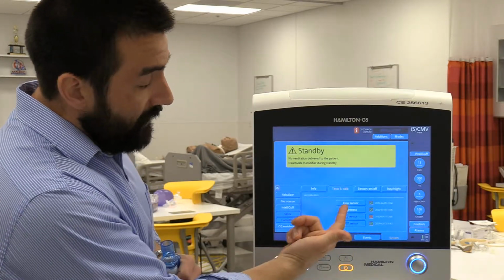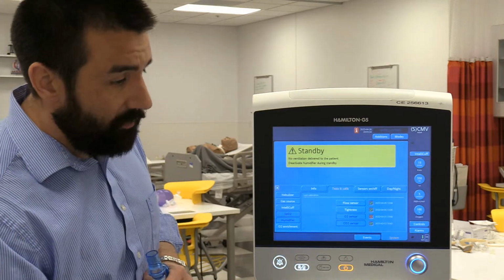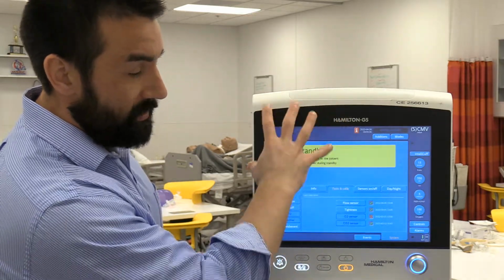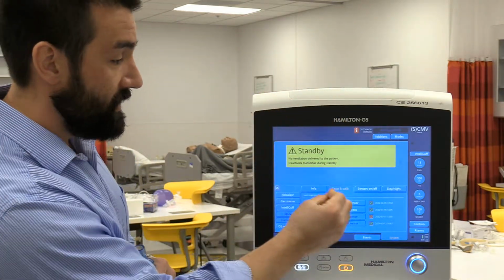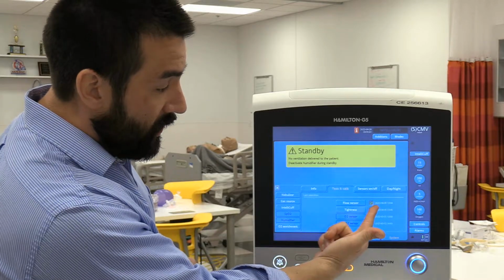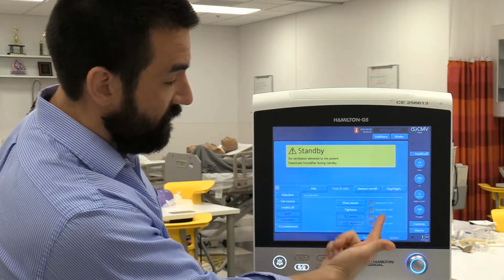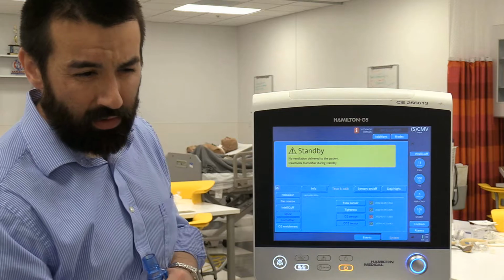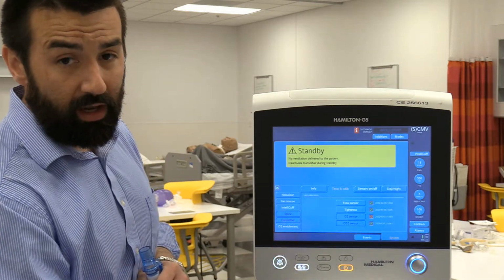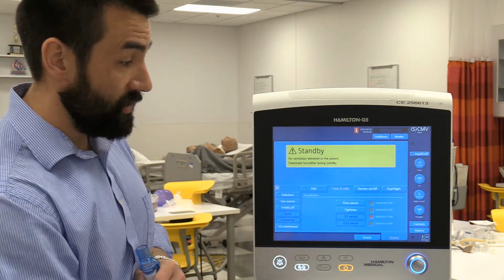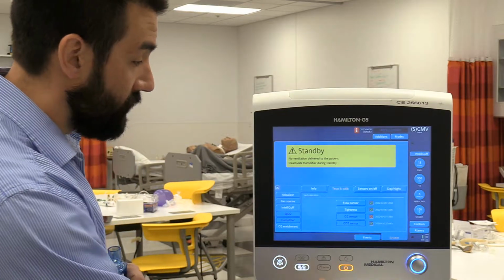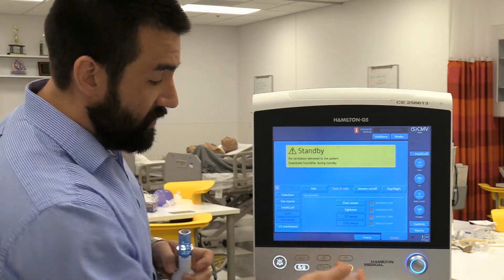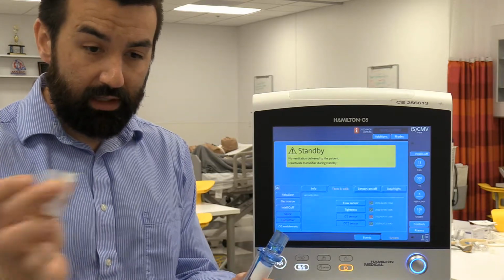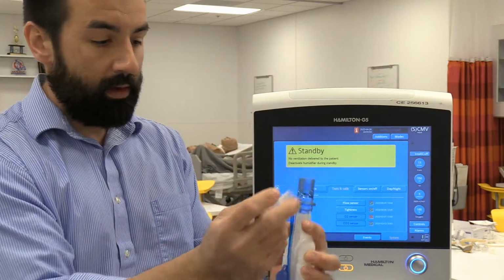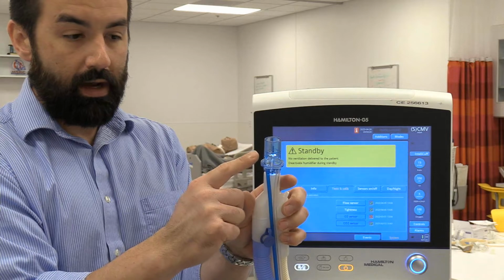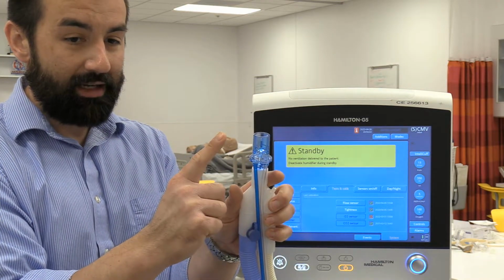All right. Hopefully your ventilators are already set up for you, but most places you're putting some sort of insignia. Hey, I checked this out at this date, and there's a sticker or something on it. You can go in and actually find when this test was performed and everything as well. Very seldomly are you doing this right before putting it on a patient, but it's always good to have a means of being able to check and make sure that this has been taken care of. Okay. So I'm going to check the flow sensor first. So the flow sensor does require this extra little piece here. Pretty much we got to be able to flip this flow sensor around and mimic gas coming from the patient side as well as the ventilator side.